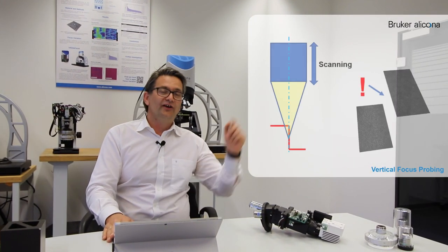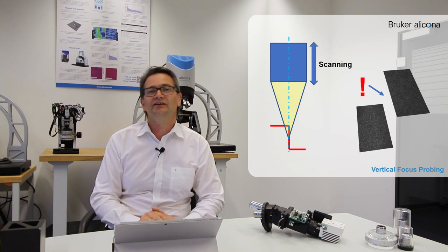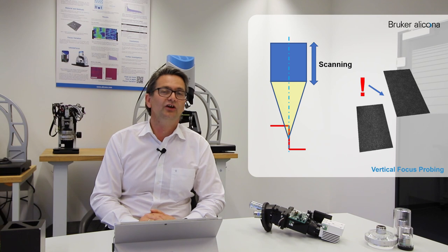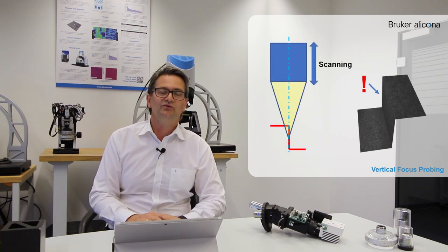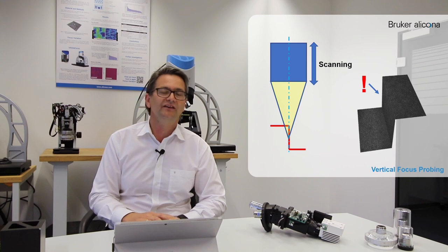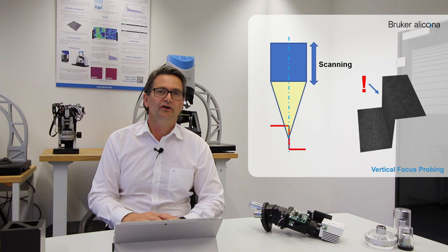Thank you. The solution is vertical focus probing. When we have the optics and use focus variation, we can measure the top surface, the edge break, angles, form, and so on — but we cannot measure the side walls. With the software extension vertical focus probing, we can also measure the side walls. I'll show you how it works. On the first diagram you see the measurement of a height step with our instrument, and you can see that by using focus variation you cannot measure the 90-degree part of the height step. With vertical focus probing, you get that 90-degree part.